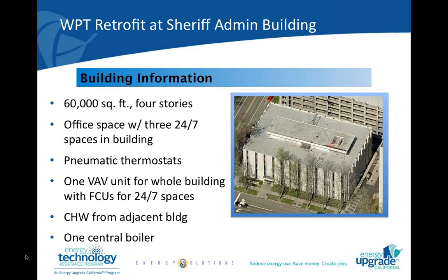A while back, they had upgraded that. There's a big air handling unit that sits up on the roof, and it serves the whole building. They put VFDs on that, and they upgraded the dual duct constant volume zones to dual duct variable air volume zones, but they are still being controlled by pneumatic thermostats. So in this case, we didn't have to pay for the VFDs, but we were still having control being done at the zone level by the pneumatic thermostats. And so we wanted to get that information at the zone level up to the building management system and then to our county-wide system. And so that's where we see the strength of these WPTs made by Cypress as being a really good fit for this facility. This facility also has a central boiler, and chill water is coming from another building. There's a central plant, and there's a set of chillers over there, including one very high efficient chiller.